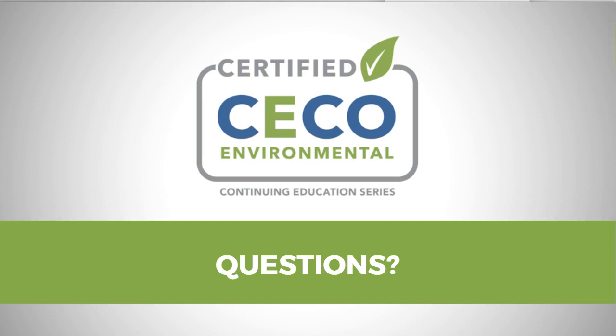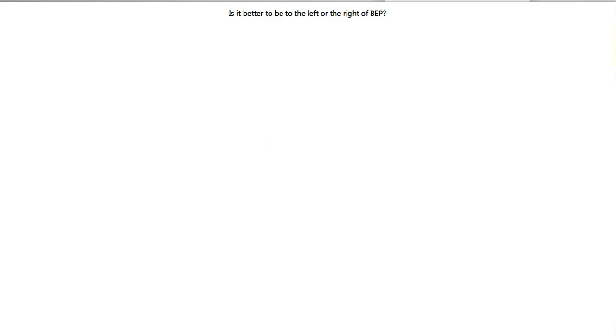So is it better to be to the left or the right of BEP? I guess I'll take that. It's kind of a trick question. It's better to be to the left of BEP just because there's more room to play there. To the right of BEP, you're increasing your NPSHR, and you're increasing your horsepower. There's more chance of cavitation if you're further to the right of BEP. You have a little bit more leeway to the left, so it is better to be to the left.